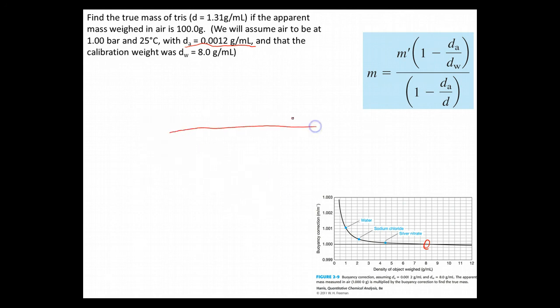Okay, so let's go ahead and set that up. We have our apparent mass that we weighed, which was the 100 grams. And notice that I've kept my sig figs in just like I should have. I like to keep track of it by writing them up with a circle for sig figs. Inside of here I have 1, which is an absolute number, no sig figs implied. Density of air divided by the density of the weight. Density of air was my 0.0012. Divided by density of the weight, which was 8.0. There we are. We never want to be sloppy and get rid of our units.